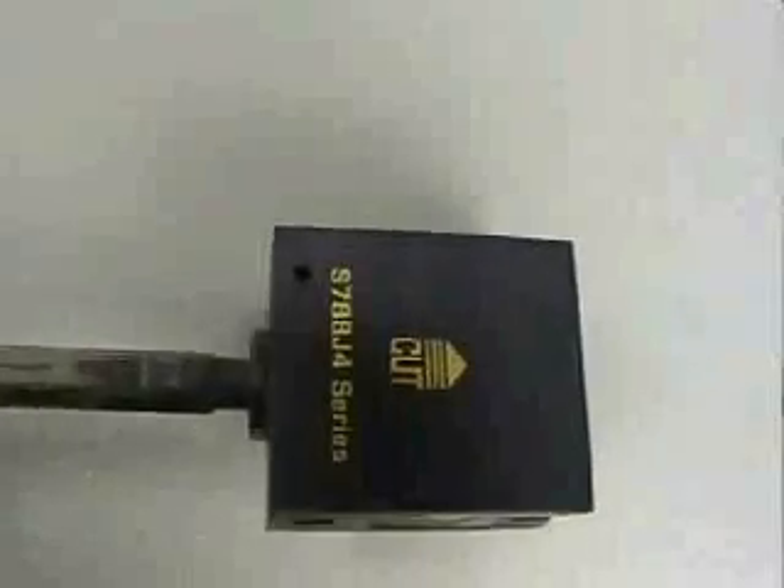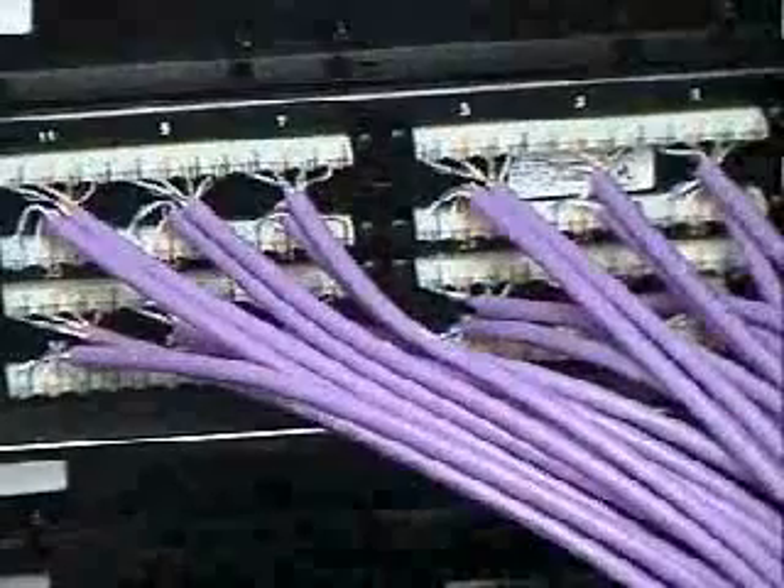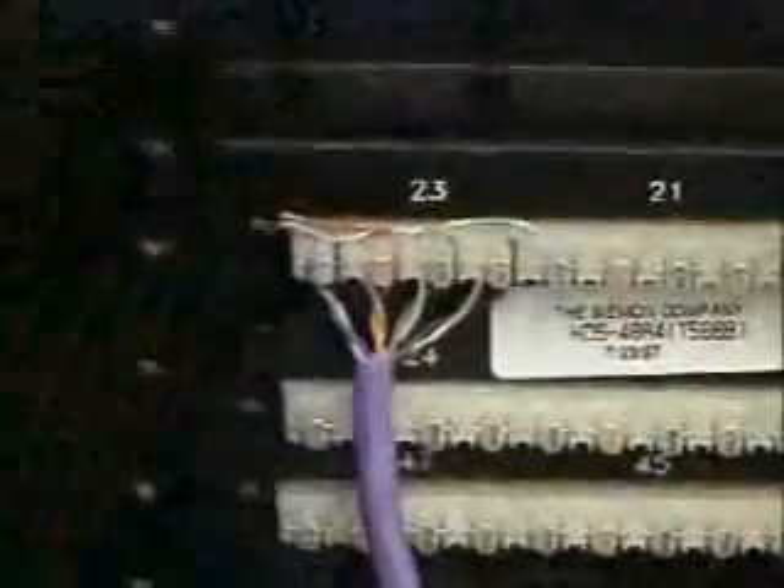To speed up the terminating process, a multi-pair impact tool may be used. Make sure the tool is positioned so that the head is the correct way round. The BICC HD5 panel is easily able to withstand the impact of multi-pair tools. Carry on terminating until all the cables on one side of the panel are in position, then repeat the process on the other side, starting from the outside positions and working towards the center of the panel.